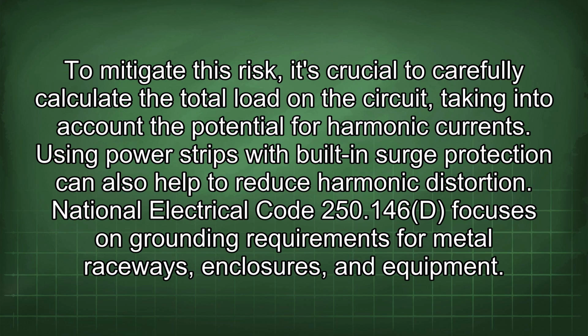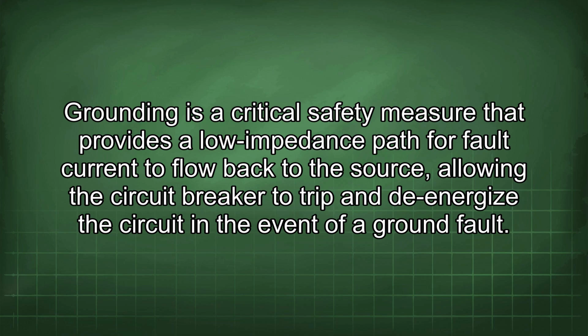National Electrical Code 250.146(D) focuses on grounding requirements for metal raceways, enclosures, and equipment. Grounding is a critical safety measure that provides a low impedance path for fault current to flow back to the source, allowing the circuit breaker to trip and de-energize the circuit in the event of a ground fault.